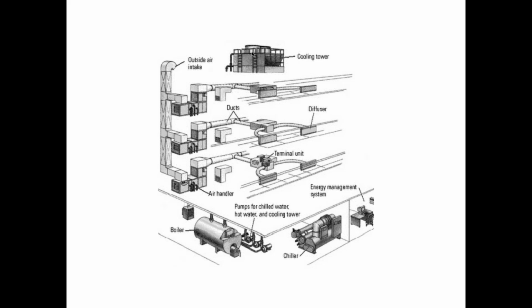Legionella, right? Legionella pneumophila loves that temperature. I think the ideal range for its growth is somewhere between 85 and 115 degrees. Perfect growth mechanism for Legionella. And not only is it a perfect mechanism for growing Legionella, it's a perfect mechanism for distributing Legionella. Why is that? Because you're spraying water and you're blowing air across the water. So what's going to happen inevitably to some of those droplets of water? They're going to get blown out of the cooling tower. Now, there's mechanisms in there called drift eliminators that are supposed to greatly reduce the amount of droplets that you blow out of the cooling tower, but they don't eliminate it. So it gets blown out of the cooling tower into the air.